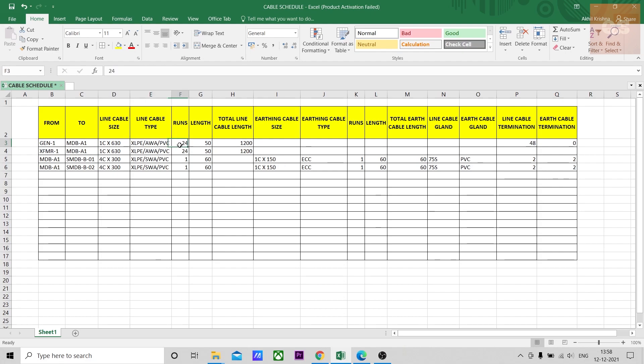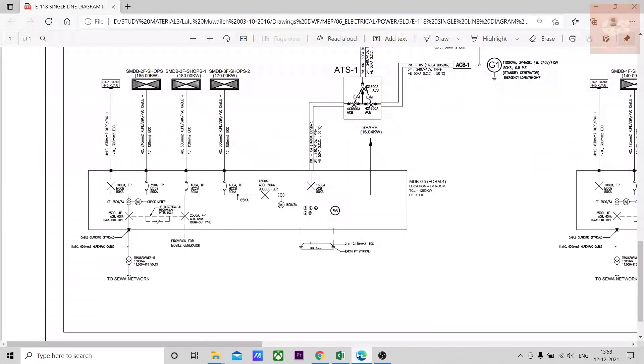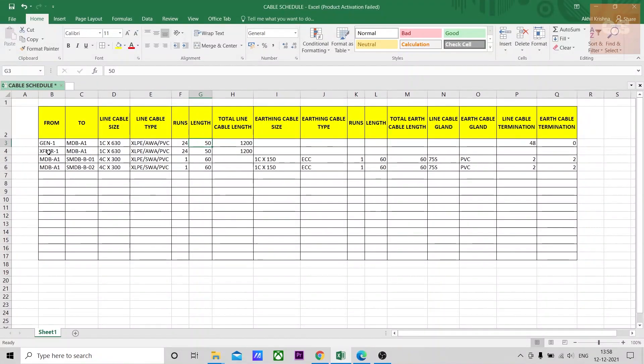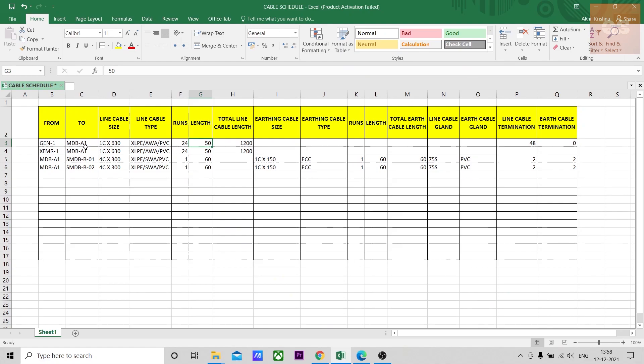Gen 1 to MDB-A1, this type of cable size is used and this is the type of that cable. Total 24 cables are there, each cable is of 50 meters. Length also, mostly for example here the length is not given. Sometimes the length will be given here. In this single line diagram the length is not given.